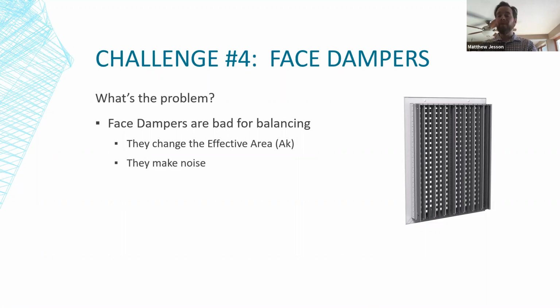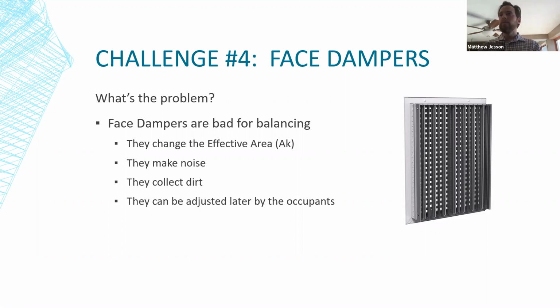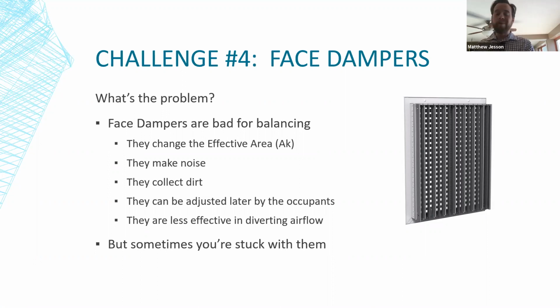They make noise, they rattle, they create air noise because they're right there at the outlet. They collect dirt and debris, they rust shut. They can be adjusted later by the occupants, which if you're the occupant, maybe you think that's a benefit, but it kind of begs the question, why are we balancing it in the first place sometimes? And they're just plain less effective in diverting airflow than a decent damper in the duct would be. But sometimes you're stuck with them.